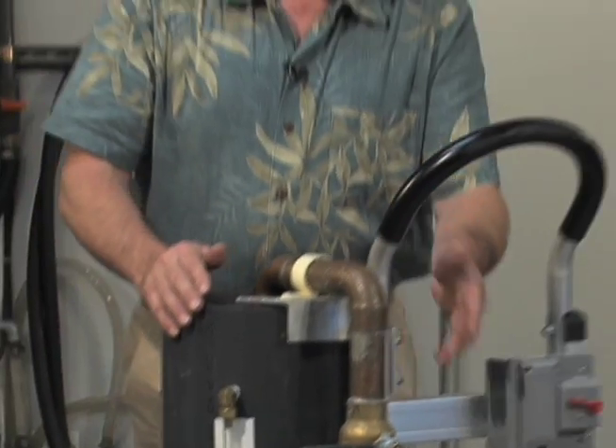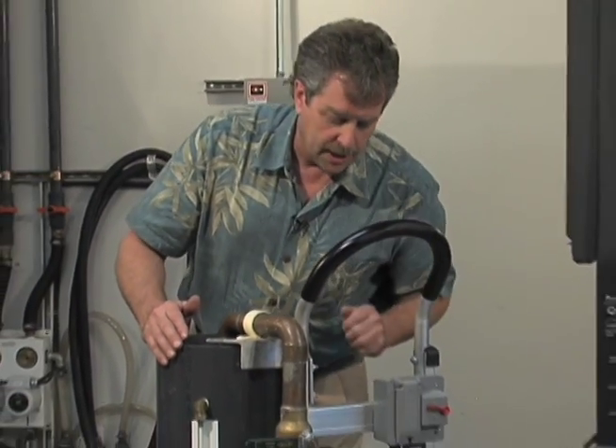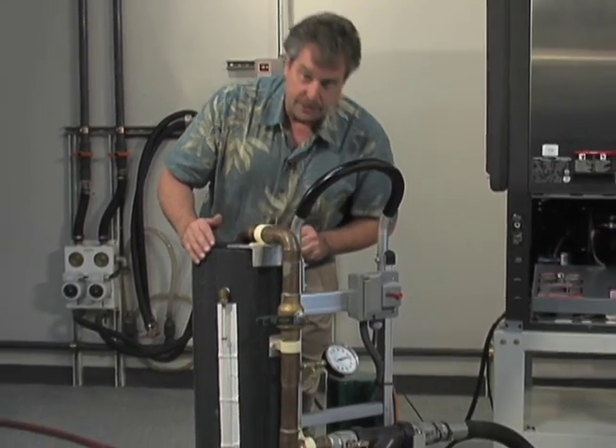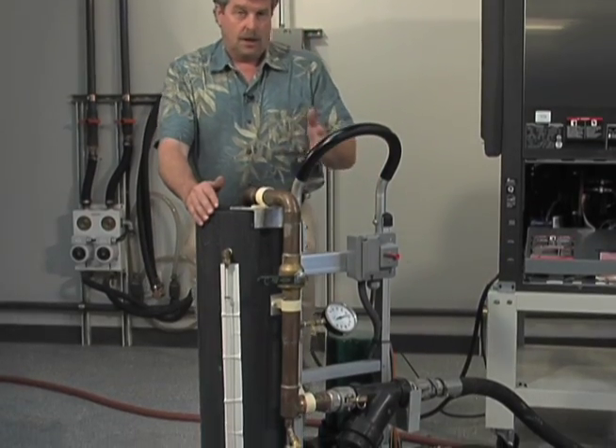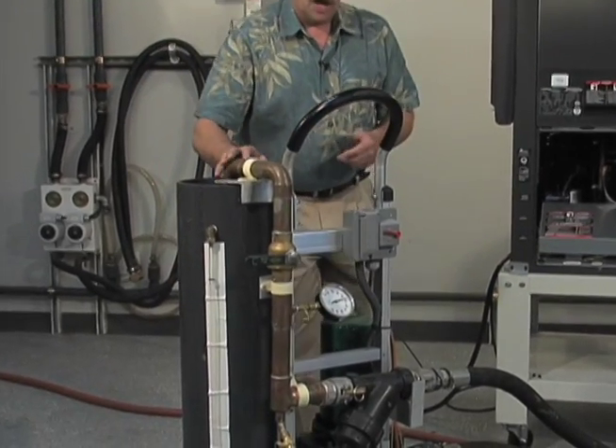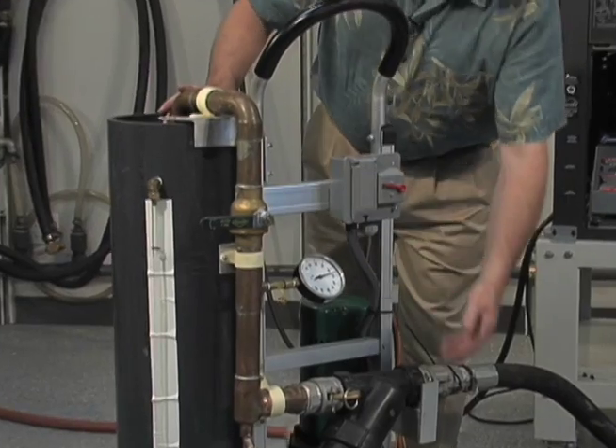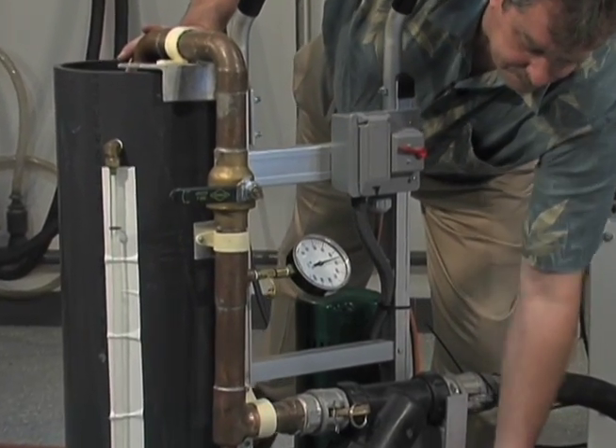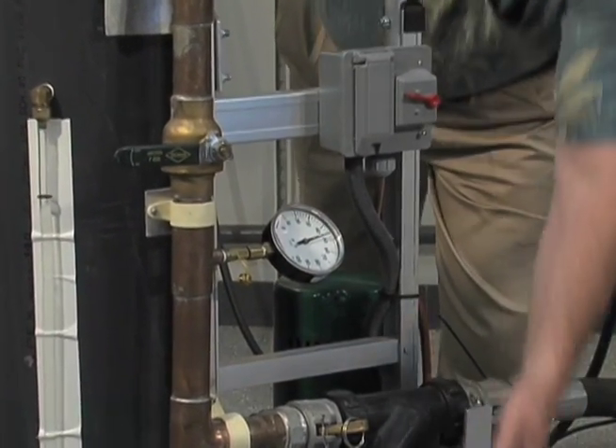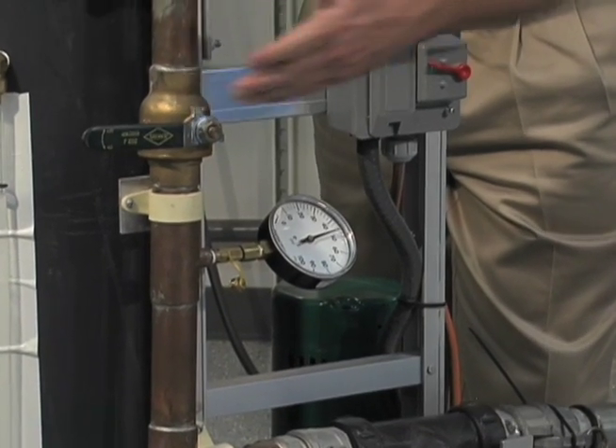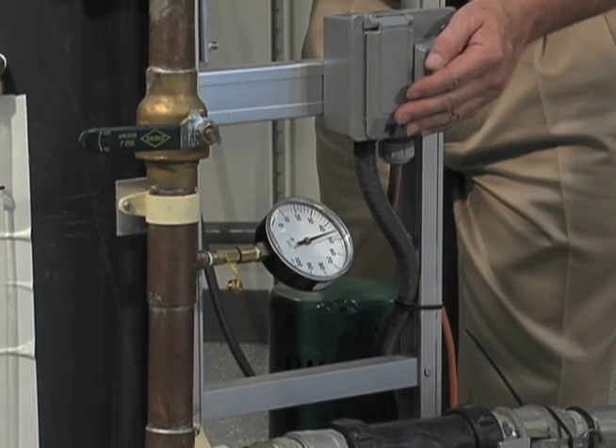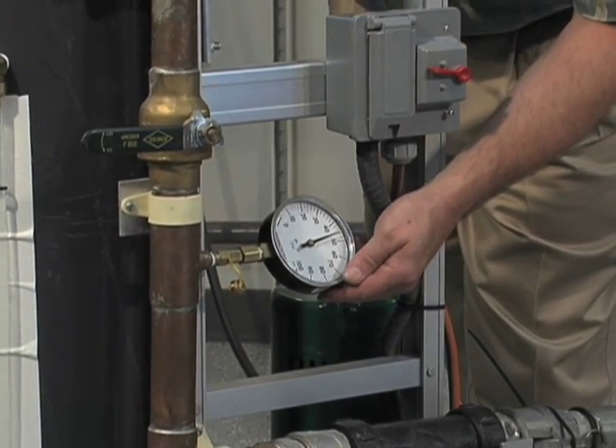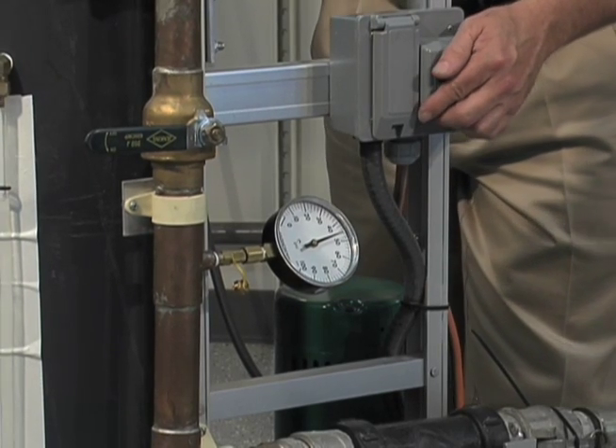So what we're going to do, we're going to again deadhead the pump. You can see our pressure gauge here is building up near 50 pounds of pressure. And I'm going to go ahead and close off the supply valve. My return is still shut off. Now I can shut the pump off. And I'm going to watch for any tail off of the pressure gauge.